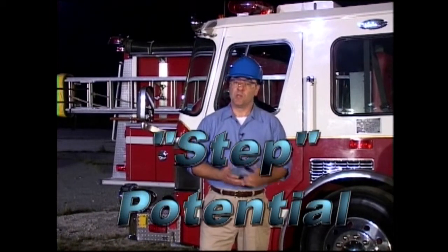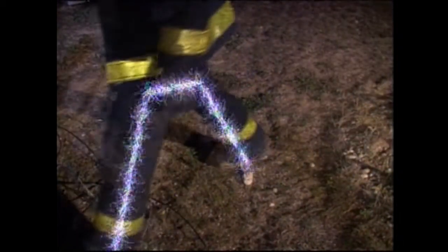As you take each step, the voltage in the ground between your feet will vary. This is defined as step potential, the voltage difference from one foot to the next, and it can be significant enough to stop your heart. When both feet are touching the ground at the same time and separated, current can flow up one leg and down the other, with the potential of electrocuting you.